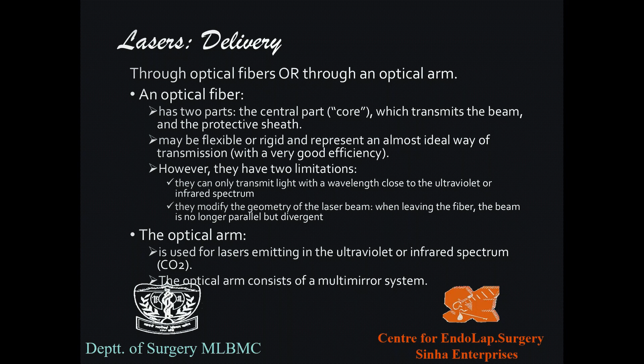Laser delivery can be through a beam via an optical arm or directly through a fiber. The optical fiber has a central core that transmits the beam and an outer protective sheath. Fiber delivery can be flexible or rigid and represents very efficient transmission — the whole laser beam is delivered at the contact point. It is ideal for endoscopic purposes. Limitations: it can only transmit wavelengths close to the ultraviolet or infrared spectrum, and when leaving the fiber the beam becomes divergent rather than collimated.